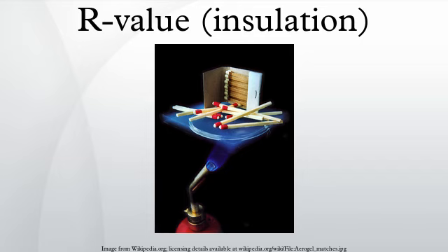The minor radiative heat transfer is minimized by having many surfaces interrupting a clear view between the inner and outer surfaces of the insulation, much as visible light is interrupted from passing through porous materials. Such multiple surfaces are abundant in batting and porous foam. Radiation is also minimized by low emissivity exterior surfaces such as aluminum foil. Lower thermal conductivity, or higher R-values, can be achieved by replacing air with argon when practical, such as within special closed-pore foam insulation, because argon has a lower thermal conductivity than air.